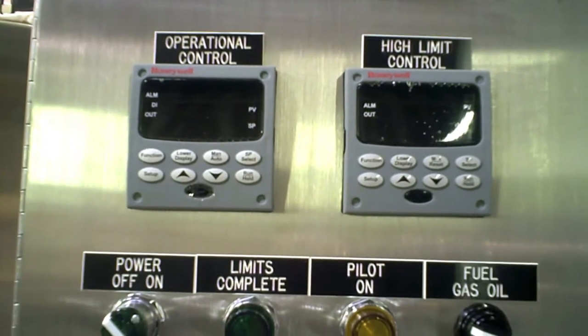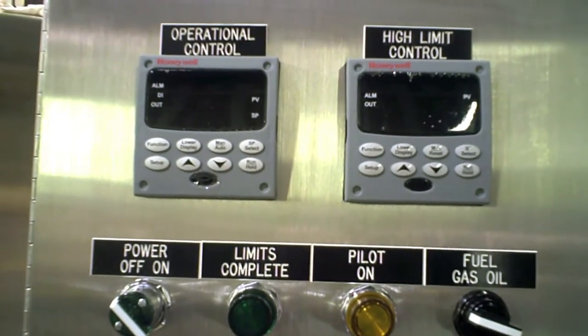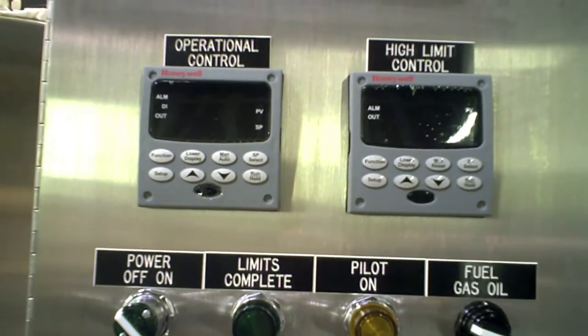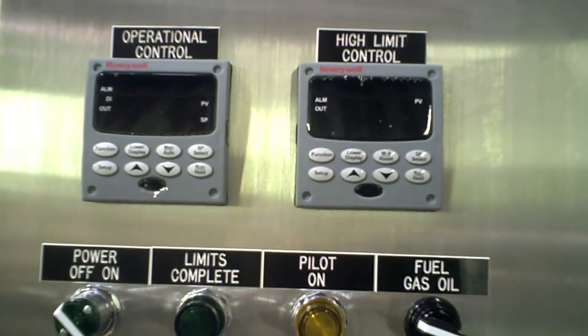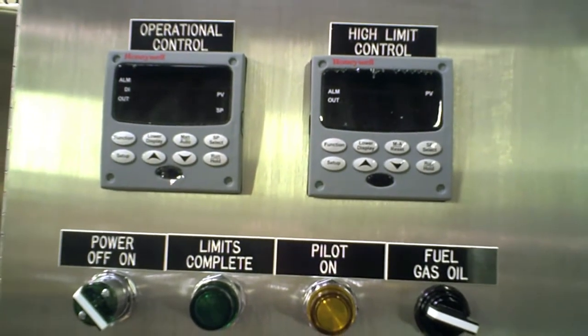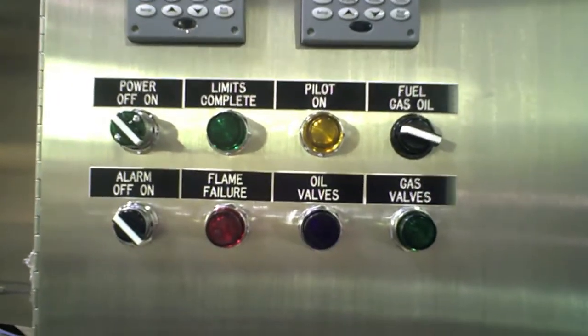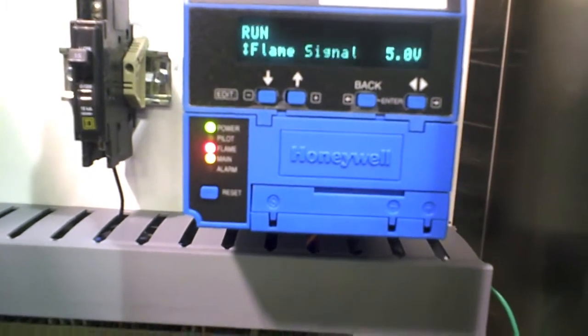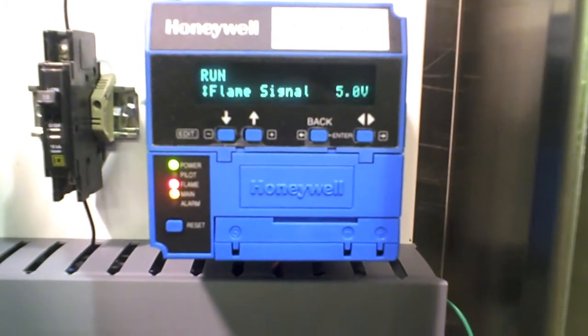The operating controls are Honeywell UDC series. The one on the left is a 3200 — it is 3-mode with remote set point and Modbus control. The one on the right is a high limit control with Modbus also; it is manual reset. The lights are standard Siemens NEMA 12 units. The flame relay is a Honeywell RM7800L with low-high-low pre-purge and UV amplifier.